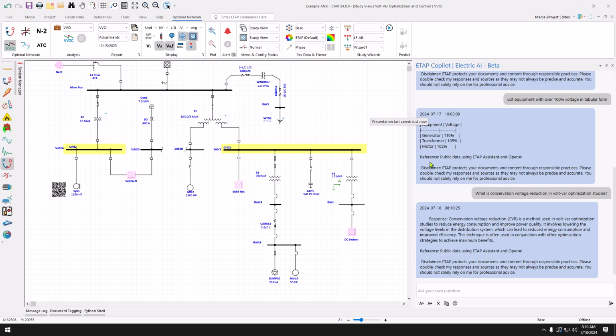Volt var optimization finds the optimum settings of voltage and VAR control devices, including LTCs, voltage regulators, switched capacitors, smart inverters, in a distribution system, and it considers objectives and constraints. The main objective really is to make this distribution system run more efficiently by decreasing power loss, reducing costs, and reducing peak demand, or as it states, conservation voltage reduction.